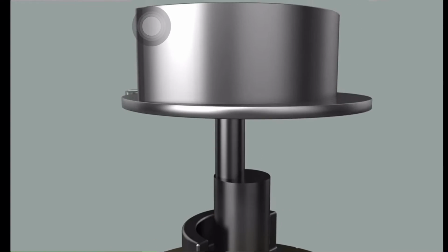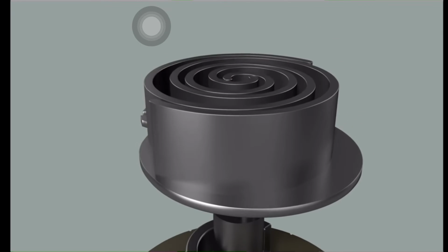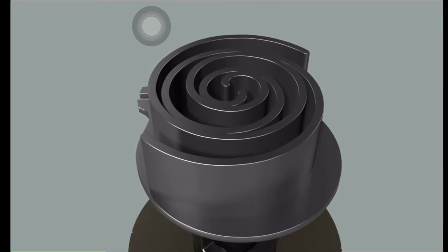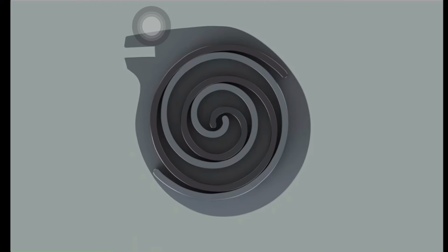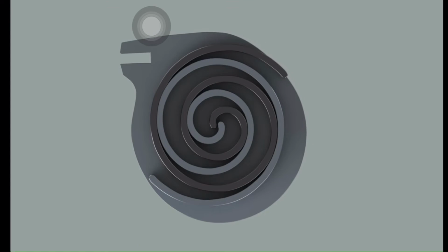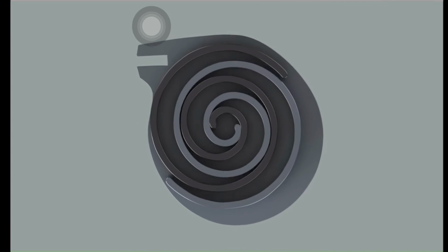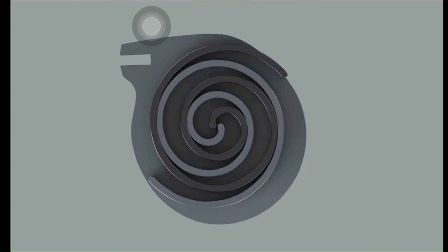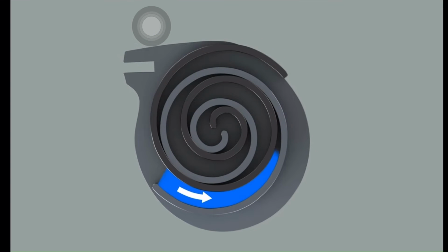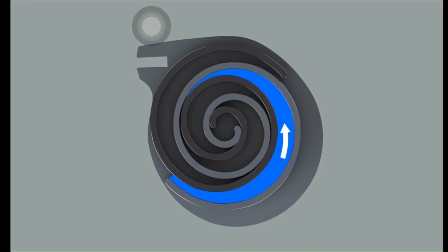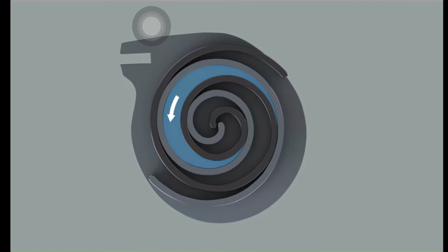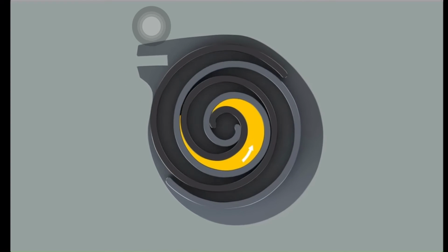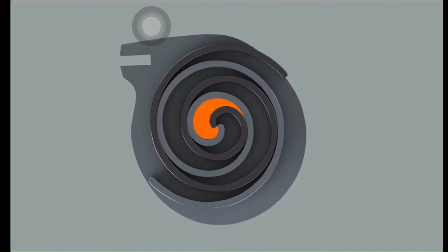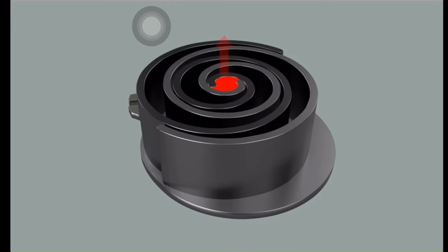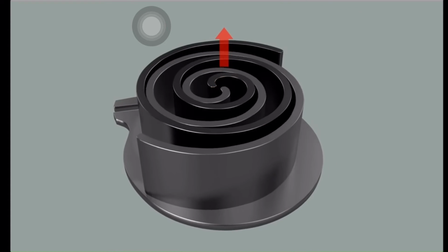However, more air conditioners nowadays use a scroll type of compressor rather than a piston type. In a scroll compressor, there are two scrolls of which one is fixed and the other rolls constantly. As more air coming through the entrance gets inside the scroll, the space becomes crowded. As there is less space now, gas becomes more compressed and is discharged from the middle of the scroll in a compressed state.